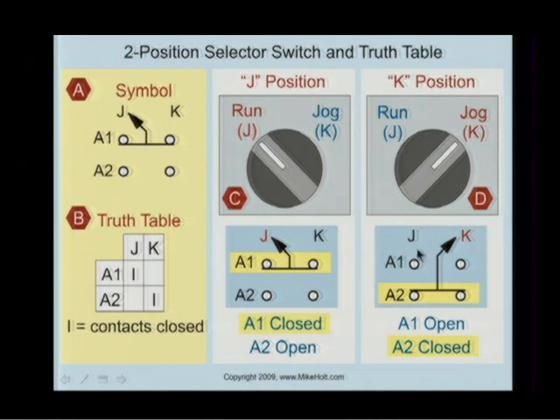But if you go to the K position, then the A1 contacts are not closed, they're open, but the A2 contacts are closed. Now, we had some discussion about this in our break time, and Steve, I think you said something about the shelf life, or one of you guys talked about why we have a truth table. Well, a truth table helps you determine which position that switch is going to be in and what kind of continuity you're going to have, because some of these can get a lot more complicated than the one that we're looking at here, where you can have a lot of different functions and so on.